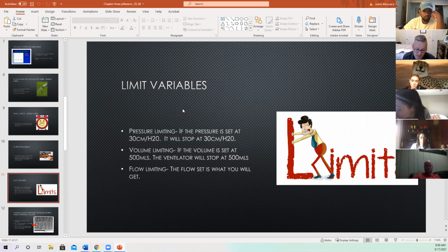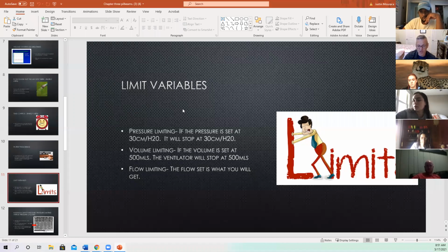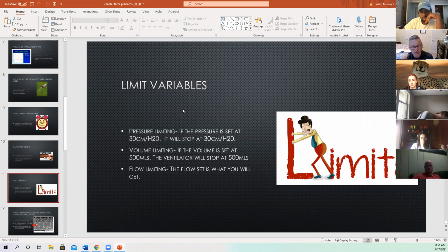Say I'm giving 500 mLs and the patient's compliance is poor. I had set my pressure limit at 30 centimeters of water pressure so that peak pressure can't exceed 30. I'm trying to protect the patient's lungs. So if I'm setting a volume of 500, I'm saying to the patient, but not out loud, if your compliance and resistance change, I'll give you that volume as long as it doesn't change so much that the peak pressure goes over 30. I won't let you have more than 30. So we have to watch, if the alarm goes off, it's stopping and that volume's not going in. The same thing applies when we set pressure control, like we were saying before. I set pressure control and sometimes the volumes drop because the resistance went up or the compliance went down. That's the same thing that's happening here. But pressure limiting is saying whatever pressure I'm setting on my alarm is where it stops. It can't go any higher.